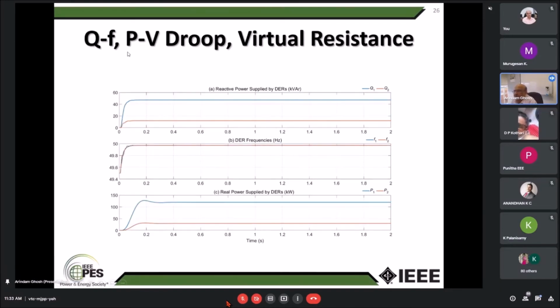And this is Q-f and P-V Droop. And virtual, this is not resistance, actually, virtual impedance or reactance or inductance. Okay, so this is wrong. Anyway, again, you can see the frequencies match, reactive power is accurate, and real power is also accurate. So that's the beauty of this situation. You can do both. To improve your real and reactive power sharing, you can put the virtual resistance or virtual impedance, which is good.